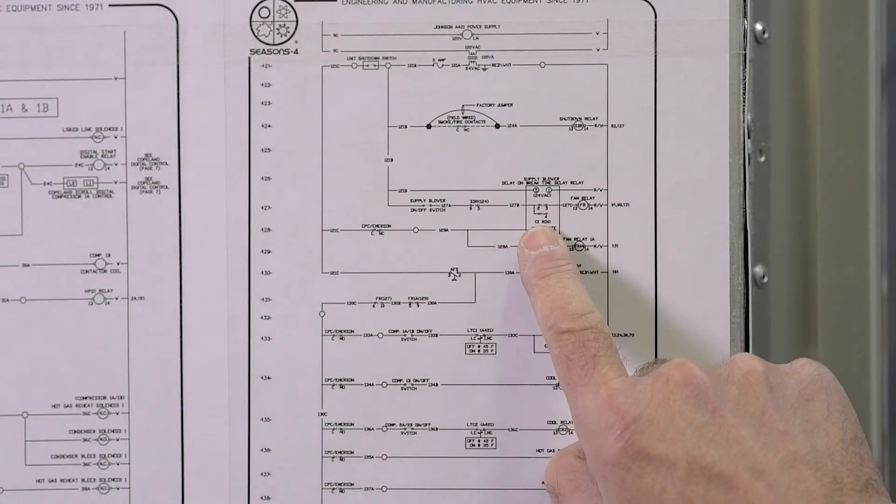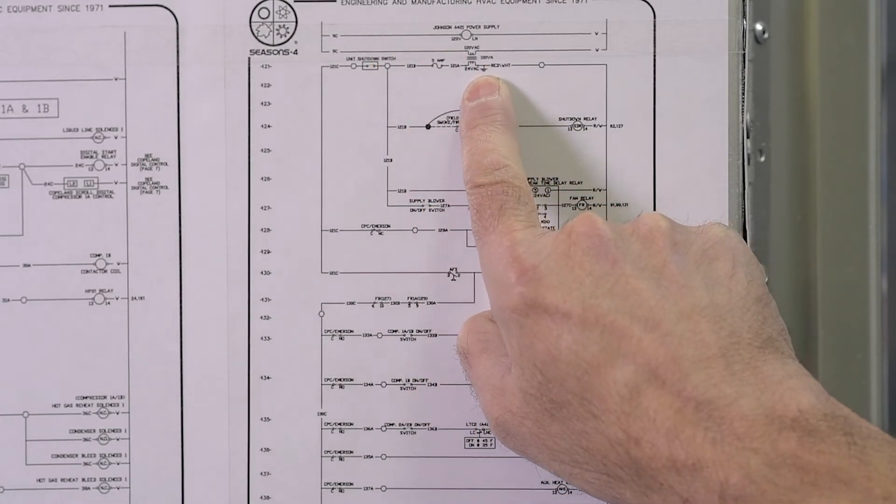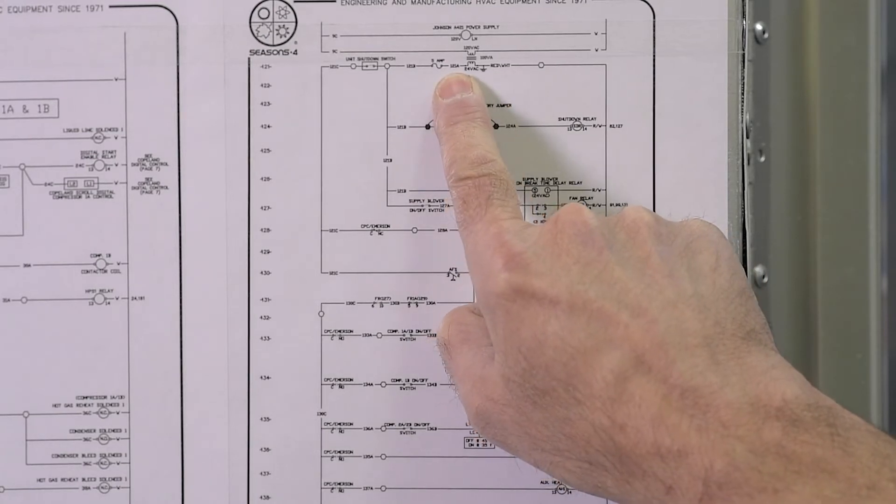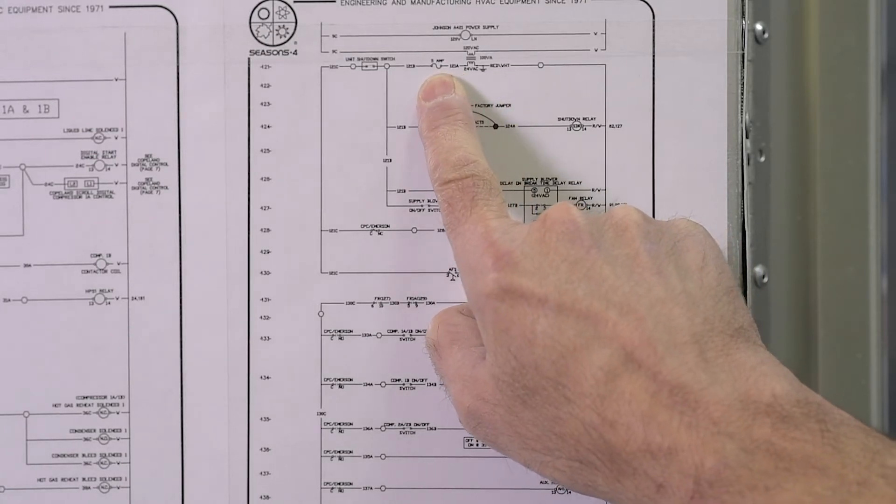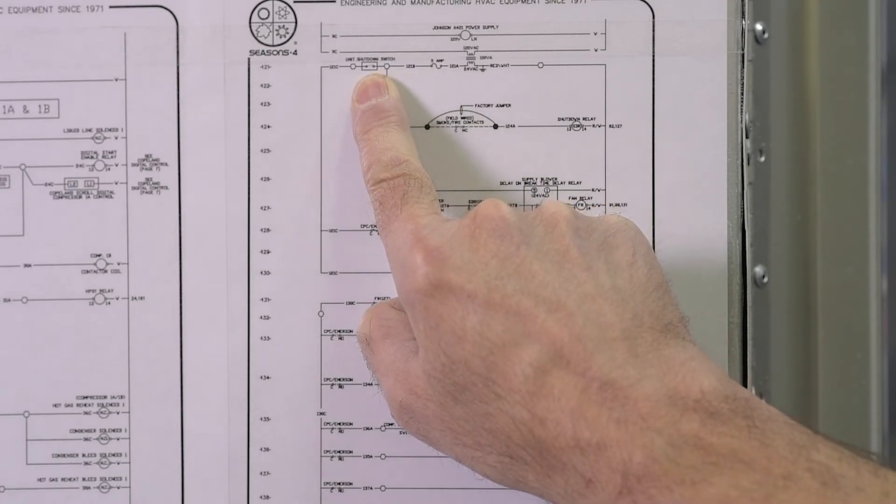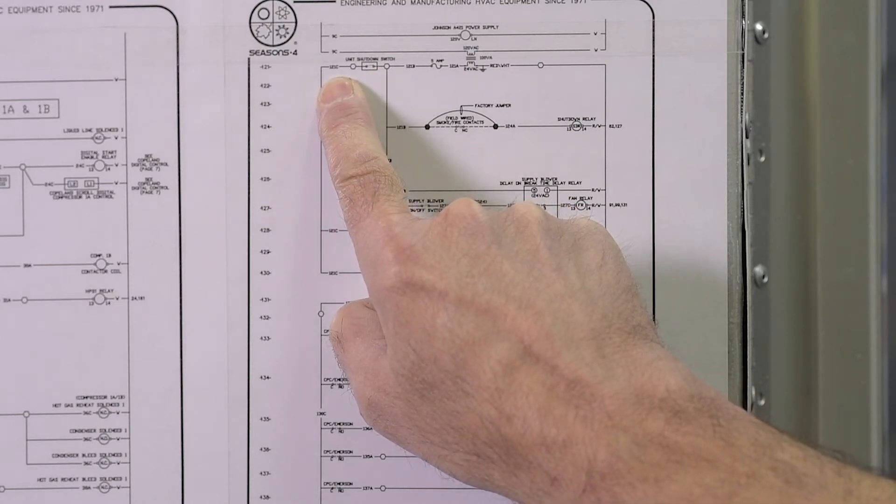This is the 24-volt page of the electrical diagram. We've got 120 volts coming into a transformer becoming 24 volts AC, a 121A that goes through a fuse and comes out at 121B, goes into the unit shutdown switch located on the outside of the control panel and comes out at 121C.